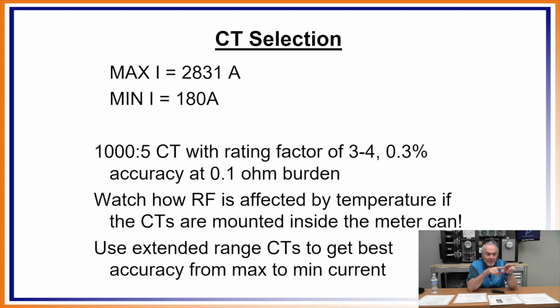Okay? Now remember, we said I've got 2831 is what I'm looking for, right? That's what I'm needing to be able to meter there. Well, guess what? My CT should be sized off of 1,000 times 3, which will get me to 3,000, gets me over my max. But on top of that, what does it do for me? Up at that upper end, remember I'm maintaining that 0.3% accuracy. Once I get over 1,000 amps on that 1,000 to 5 CT with a rating factor of 4, we'll just say 4, then as soon as I get over the 1,000 amps, I stay 0.3% accurate all the way up, right? So up to 4,000. So in this case, you could get a 3 or a 4 rating factor on it, and it would cover you on the 2831. It would maintain that high accuracy for you.